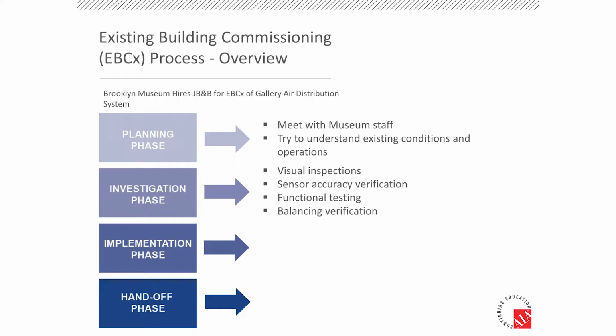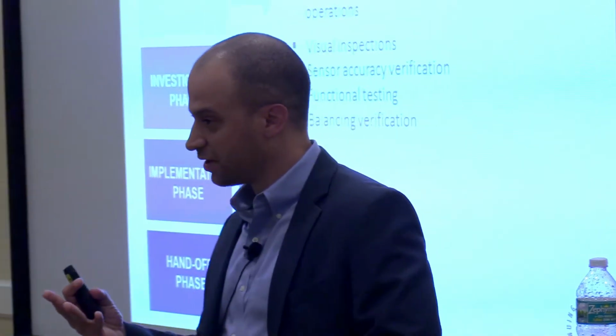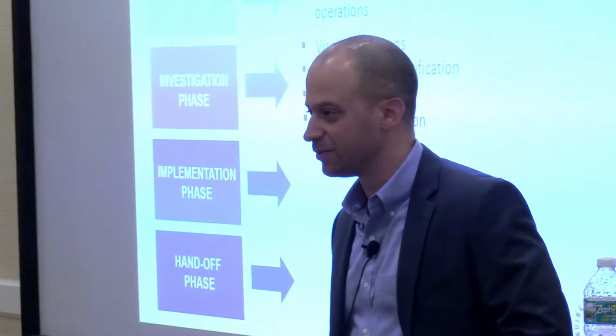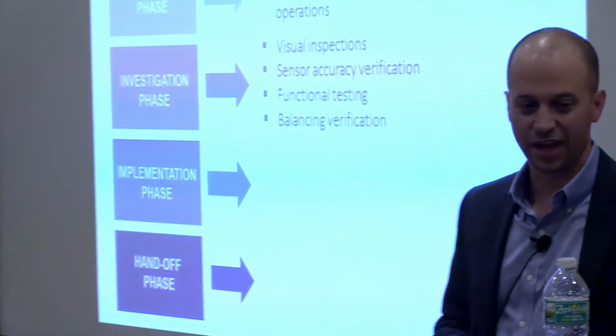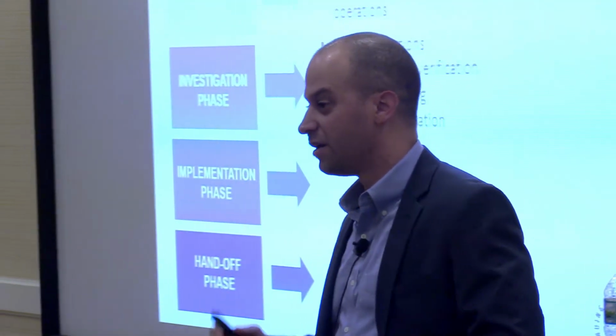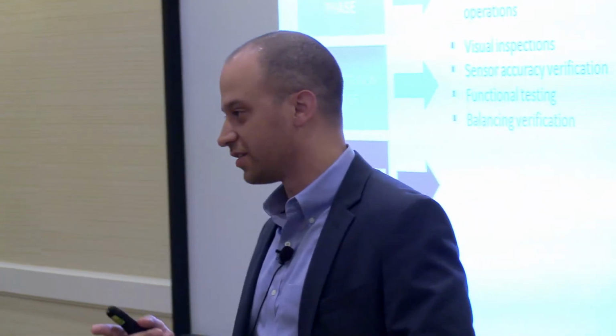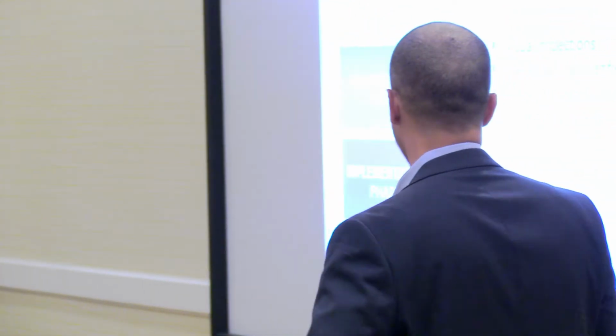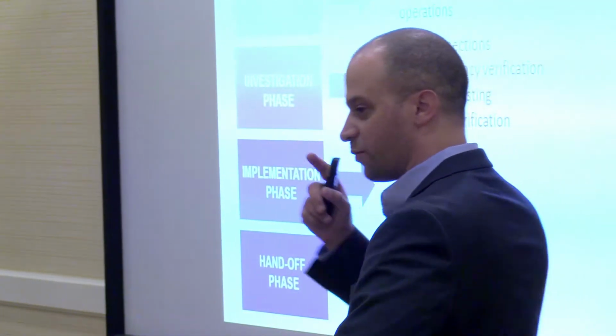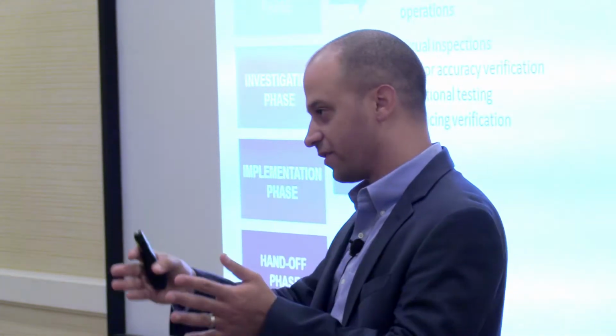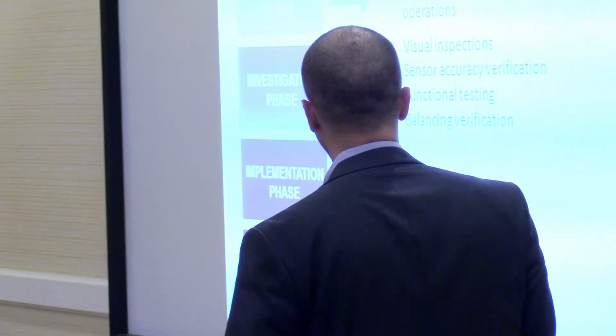The investigation phase is more of the functional testing we talked about, for new building commissioning and existing. That's where we do the bulk of the actual investigative work. We put eyes on everything. I hope no one in this room commissions from a computer, because I do see a lot of people doing that. I imagine no one here is smart enough to do that. But put eyes on everything—if the BMS is telling you a damper's opening, you better make sure that damper's actually opening. So that was the first thing, and again we went from individual component to system level to trend.